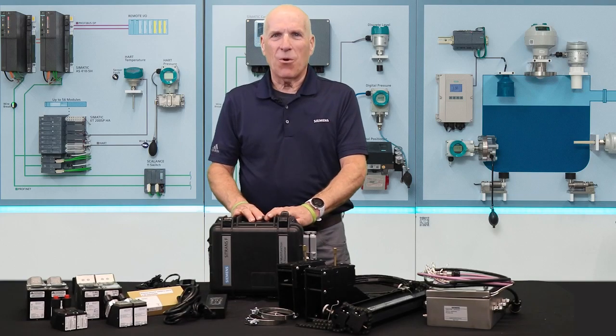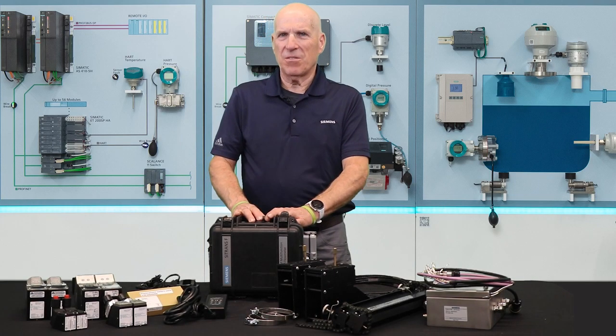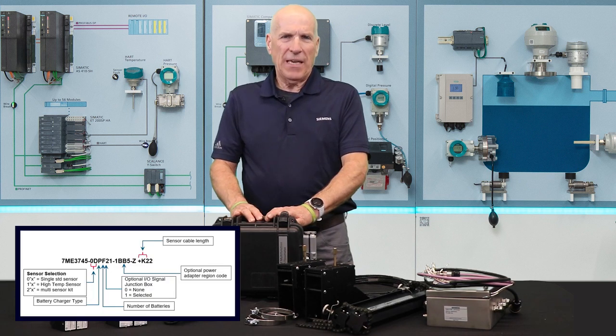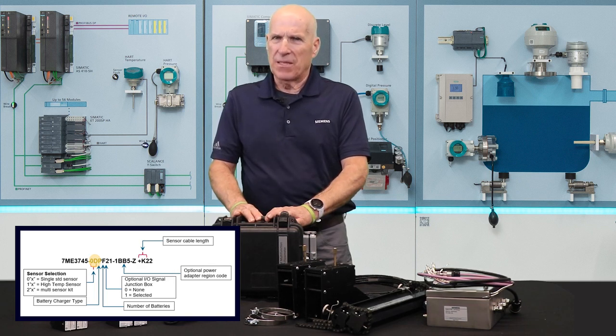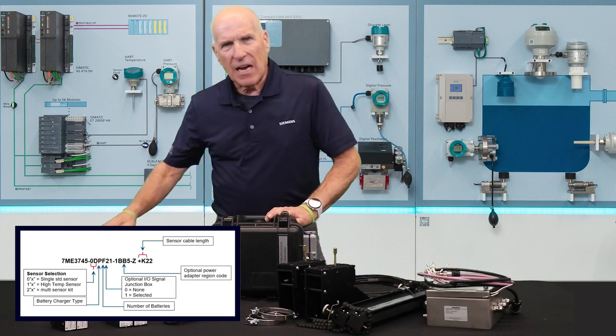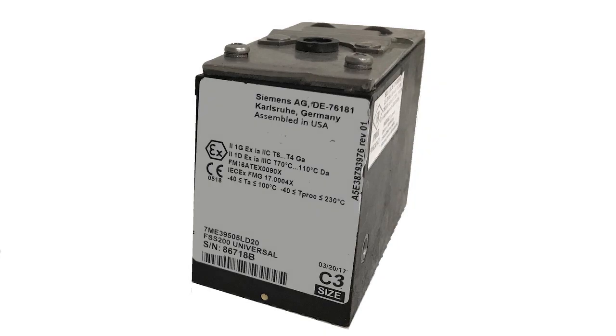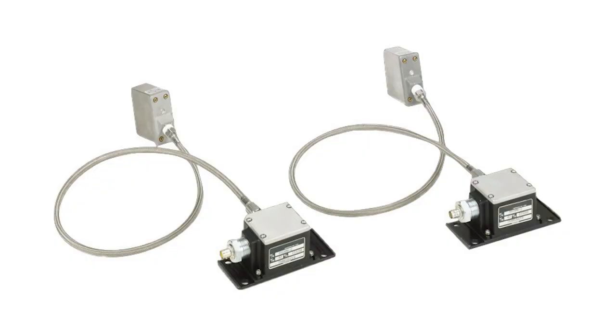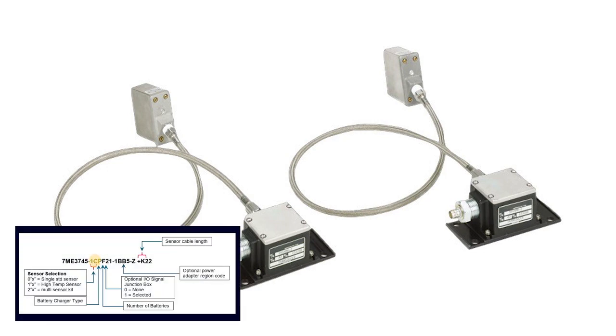If your flow meter was ordered with just a single set of flow sensors, standard flow sensors would be indicated by a 0 and a letter. The 0 represents standard temperature range up to 250 F, while the letter represents the sensor type and size. For example, a 0D would be a size C3 universal sensor. Sensors are selected at the time of ordering. High temperature sensors are indicated by a number 1 and a letter. The letter represents the sensor size. For example, 1C would be a size 3 high temperature sensor.